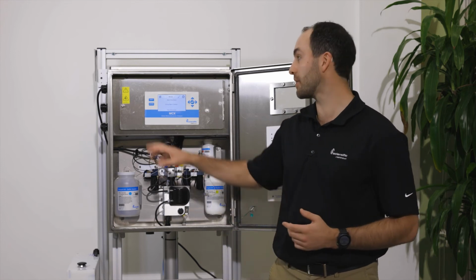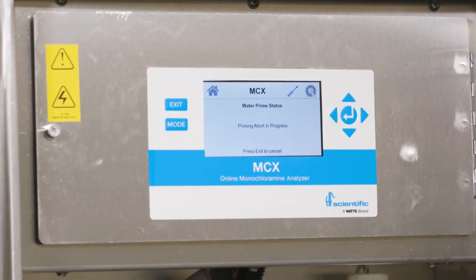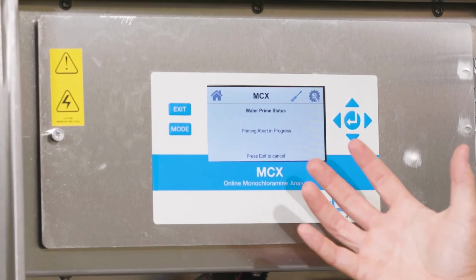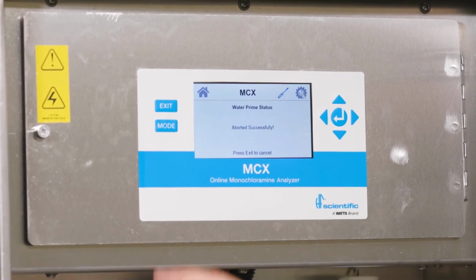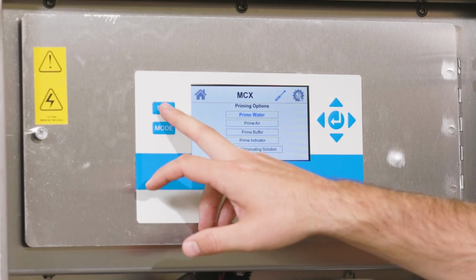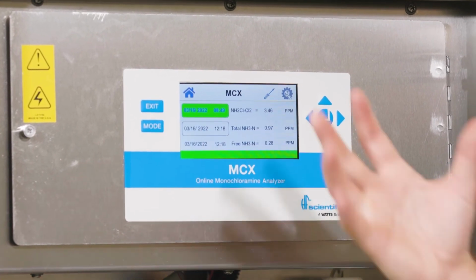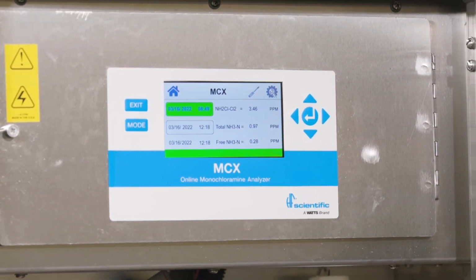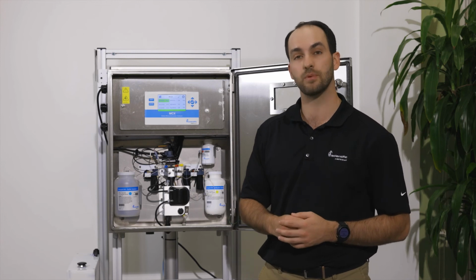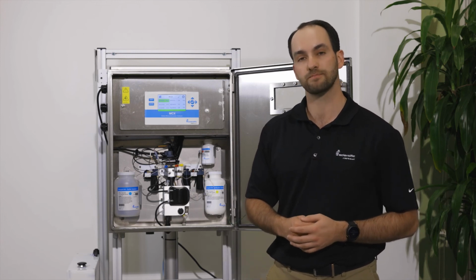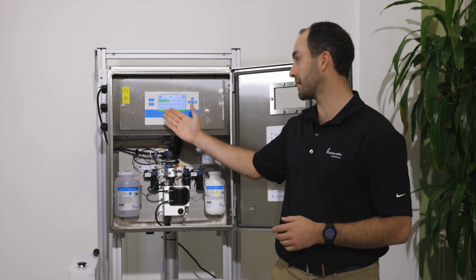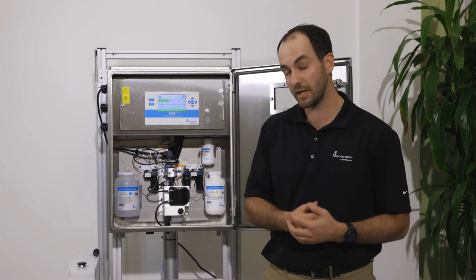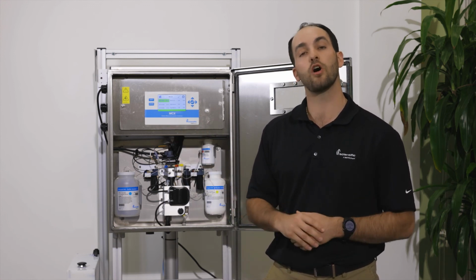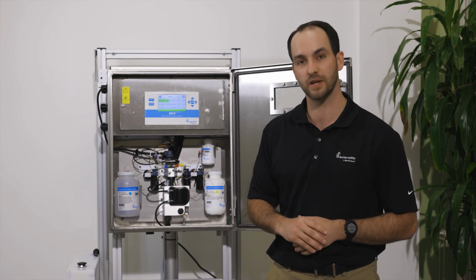To go to normal operation, click Exit to abort the water prime, and once you get back to the prime screen, you will press Exit again, and one more time to get your analyzer back into normal operation. If you have the analyzer in grab sample mode, you'll be prompted to pick which option you'd like. If you have the analyzer in continuous operation mode, the analyzer will automatically go back into a 15-minute cycle.